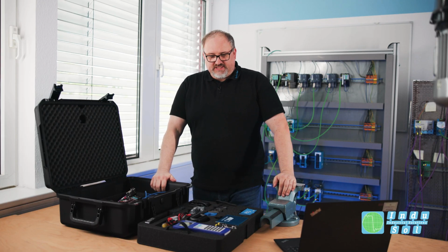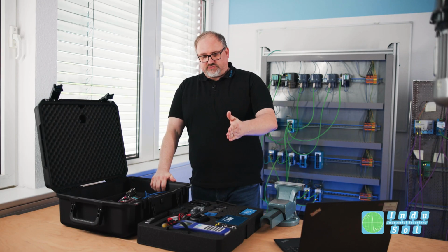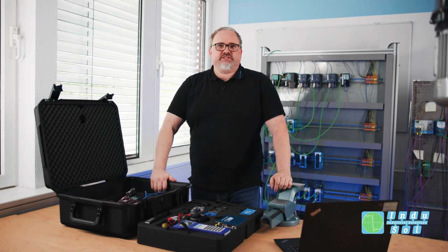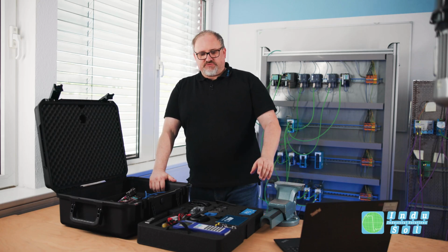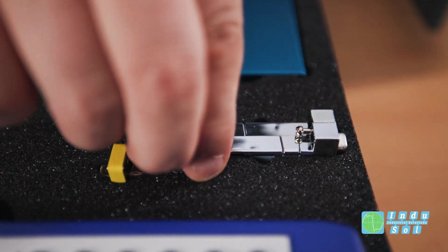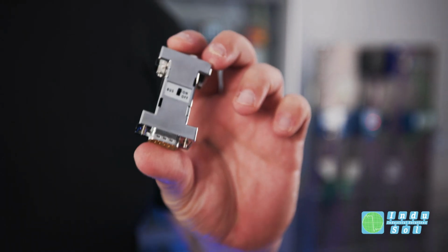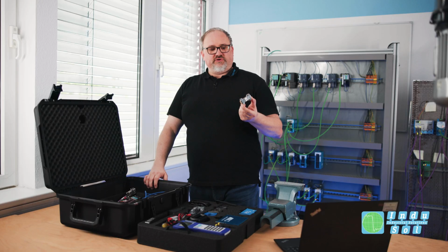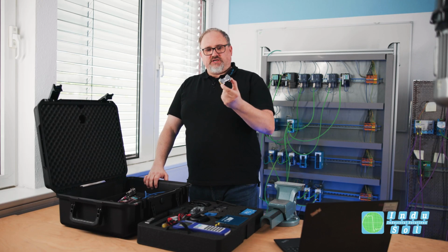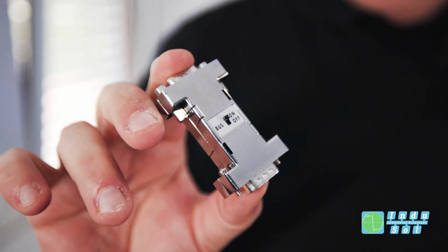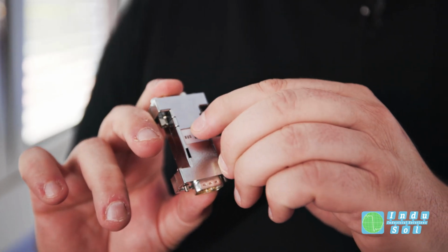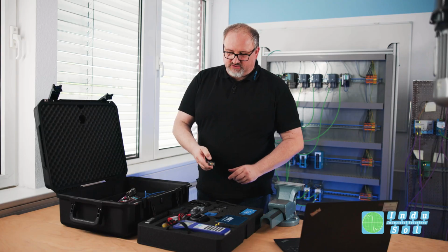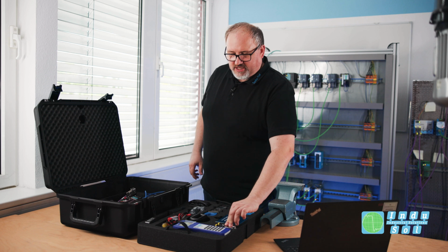What else do we have? The last thing would be, if you want to conduct the line test, it includes the terminating resistors. These must be powered in the PROFIBUS. If your control system, for example, is located at one end, you would need to interrupt the communication accordingly, but ensure the power supply. For that, there is the so-called bus separator, right? So this large silver adapter piece.